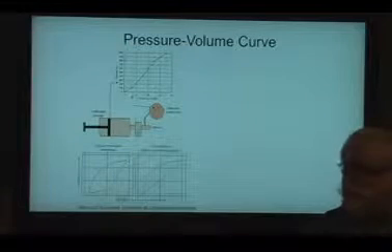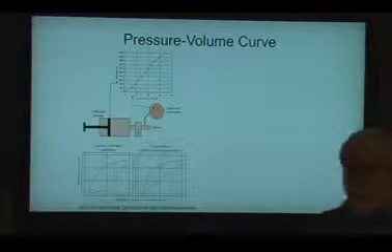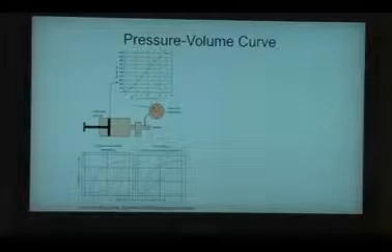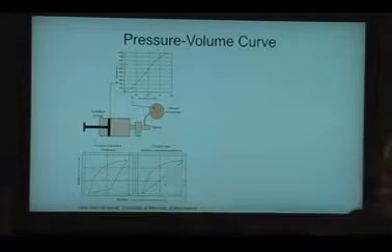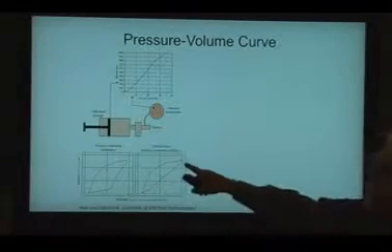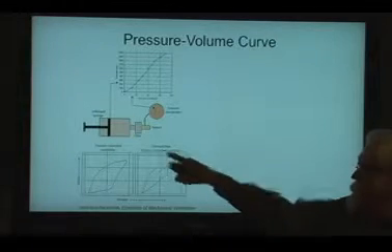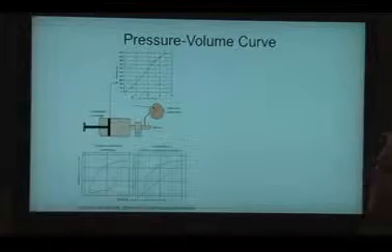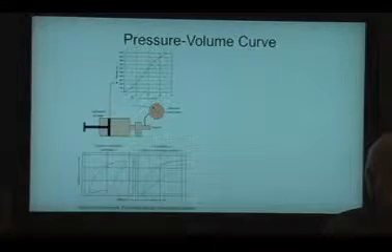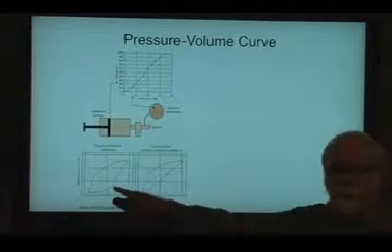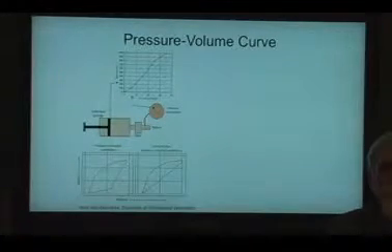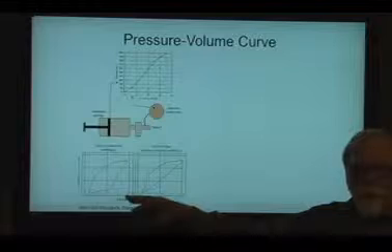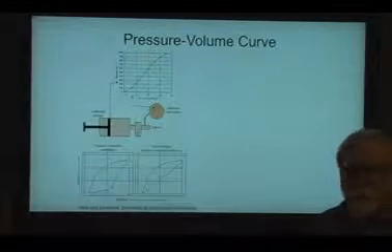These are some curves that I generated off of a lung model probably 20 years ago now, on the table right in front of where Patty's sitting, and they illustrated very nicely what the PV curve looks like on the ventilator with constant flow volume control ventilation. And if you switch the ventilator to pressure control, with the same tidal volume and the same peak, it looks like there's a lower inflection point when there is really not, because this is a function not of the elastance of the system, but of how the ventilator delivers flow during pressure control.